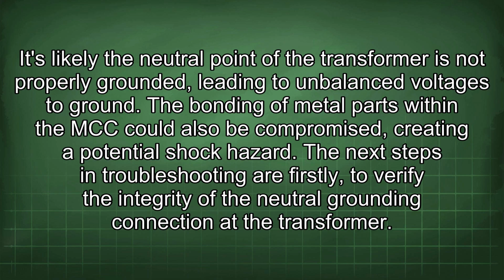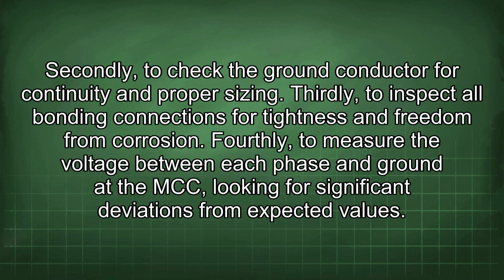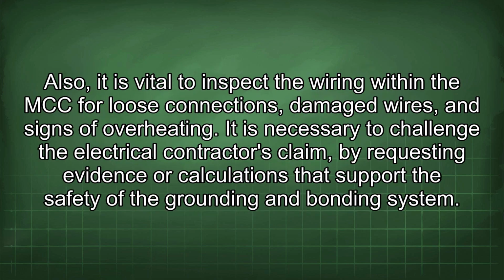The next steps in troubleshooting are, firstly, to verify the integrity of the neutral grounding connection at the transformer. Secondly, to check the ground conductor for continuity and proper sizing. Thirdly, to inspect all bonding connections for tightness and freedom from corrosion. Fourthly, to measure the voltage between each phase and ground at the MCC, looking for significant deviations from expected values. Also, it is vital to inspect the wiring within the MCC for loose connections, damaged wires, and signs of overheating.